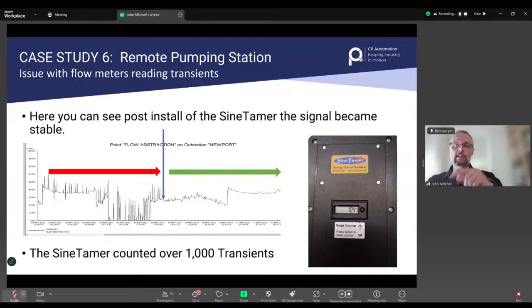So this SineTamer was not put on the sensor signal. It was put on the main supply of the incomer to that panel, and it cleared up everything inside the panel, and then it worked seamlessly.